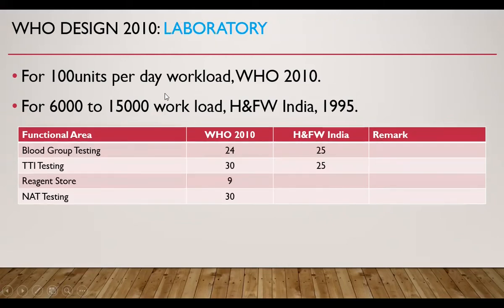For the Laboratory Unit at 100 units per day workload, the WHO 2010 document recommendation is 24 square meters for blood group testing, 30 square meters for TTI testing, 9 square meters for reagent storage, and 30 square meters for NAT testing.